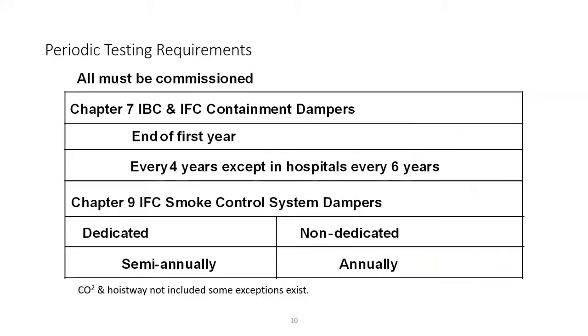Here are the periodic testing requirements. There are some exceptions, particularly in the smoke control, because you don't want to be closing a damper or opening a damper and causing any damage to ductwork. But Chapter 7 dampers, which are the containment dampers, and about 90% of those installed after commissioning, got to test them at the end of the first year, and then every 4 years, except hospitals every 6 years. I know that's sort of backwards, but hospitals are very good about taking care of things, and commercial buildings are not good about taking care of their dampers. But that's primarily because we have enforcement there on a regular basis, right? Yes. The Joint Commission inspects hospitals and makes sure that they're in good shape.